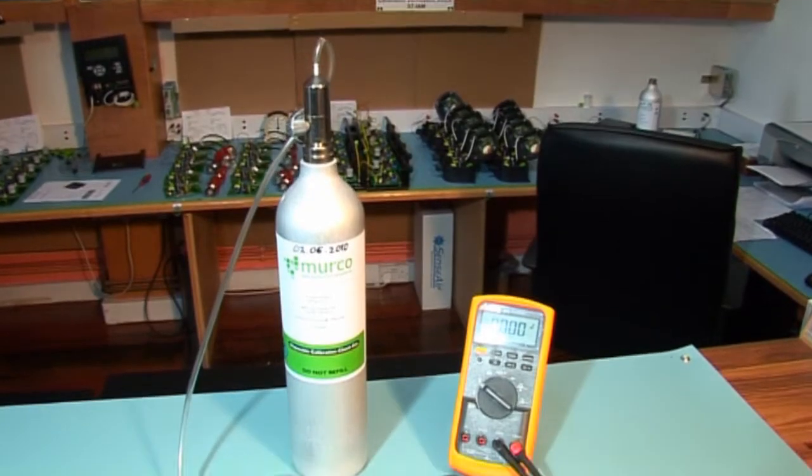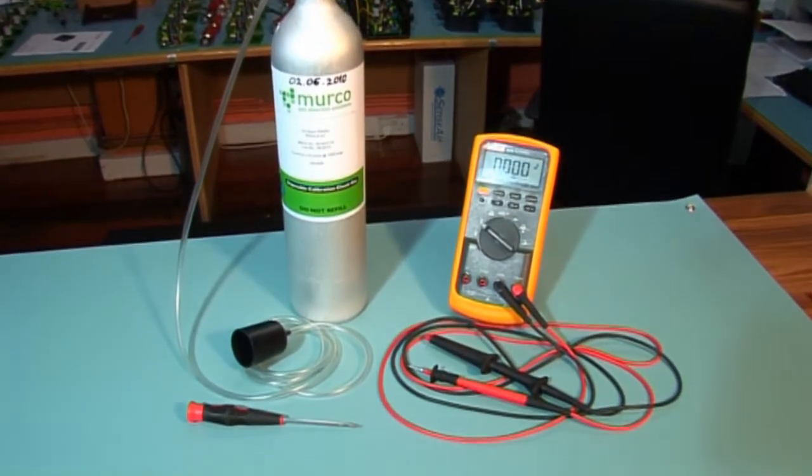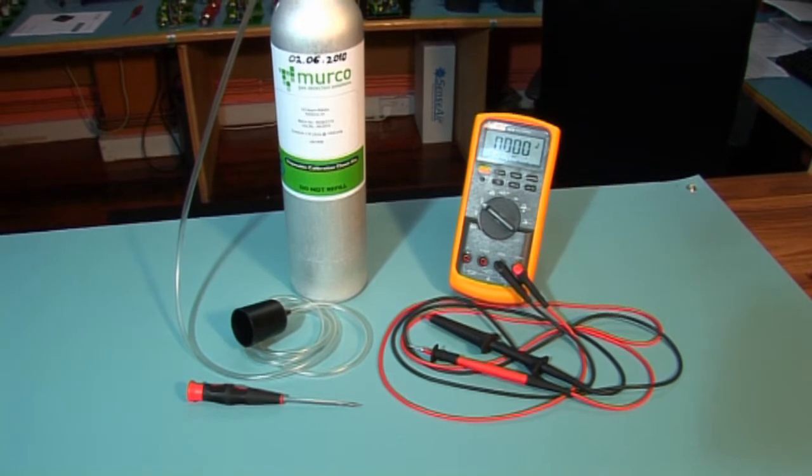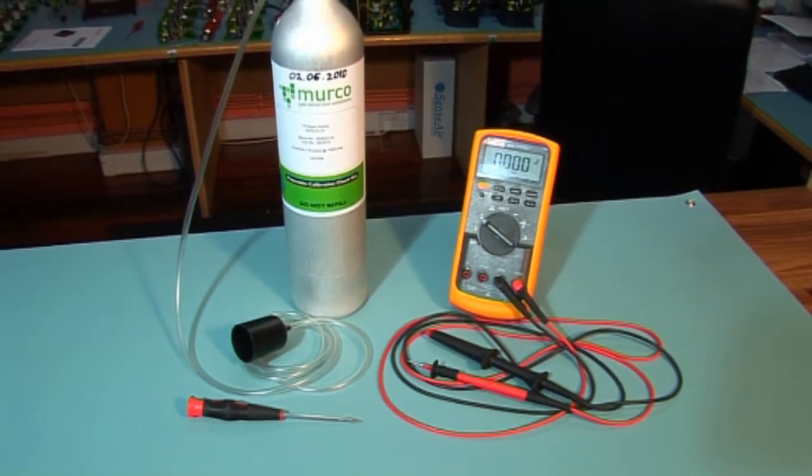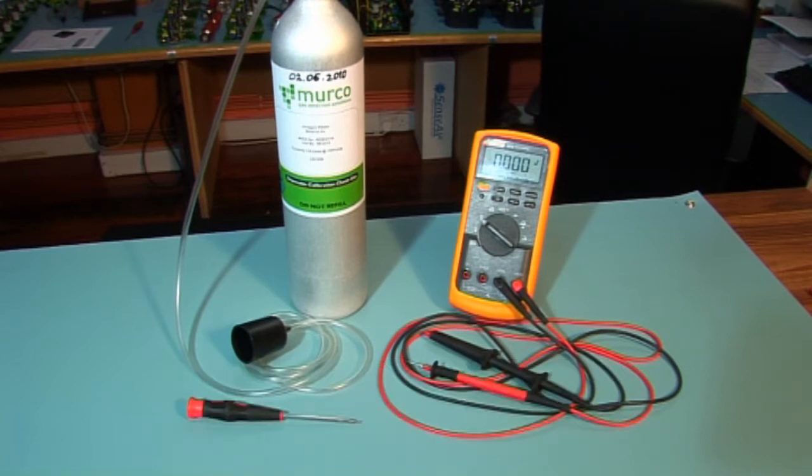The tools required are a digital voltmeter with a resolution of two decimal places, a crocodile clip, a flat-bladed screwdriver and a Murco calibration kit, which includes your cylinder of calibration gas, flow regulator, flexible non-absorbent tubing and a vented calibration hood.